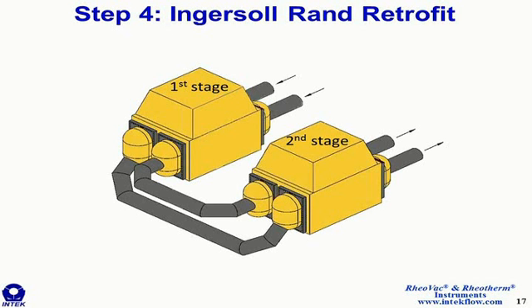This is that condenser, a top view of that condenser. It's a two-shell condenser. The cooling water enters the first stage up at the top, flows through the first stage, picking up heat, condensing steam, enters the second stage and goes to the second stage. Both shells are isolated, so the second stage operates at a higher pressure than the first stage. Both of these condensers are attached to LP turbines.